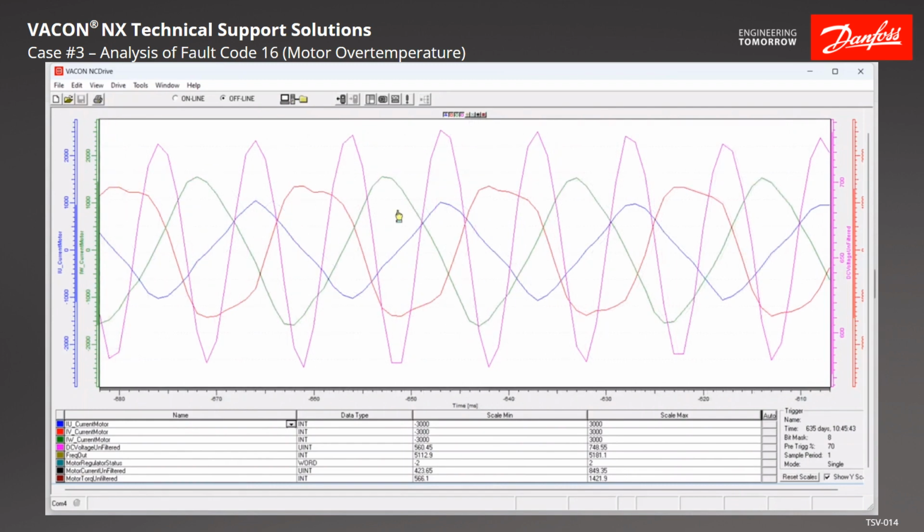As we look at our currents and DC bus, all of our currents are scaled on the same level, 3000, 3000, so they're all scaled. If you get some weird scalings, you may have to type in the scalings down here to make them all look even. Now the DC bus looks like a sinusoidal waveform. That's our pink waveform here. And that looks like an awful big ripple on the DC bus. So let's figure out what's going on with the DC bus.